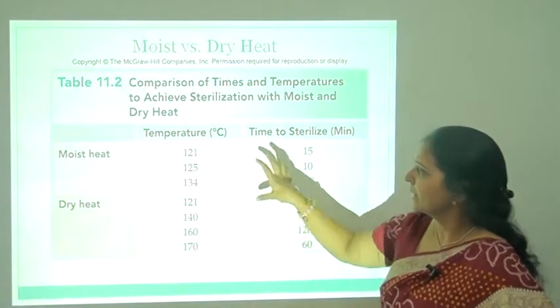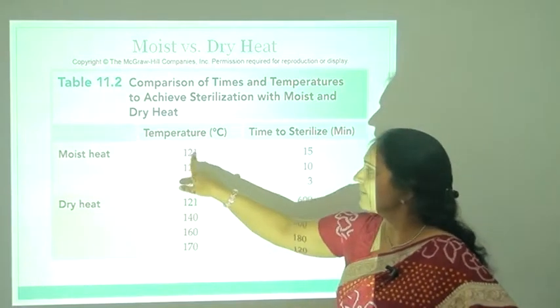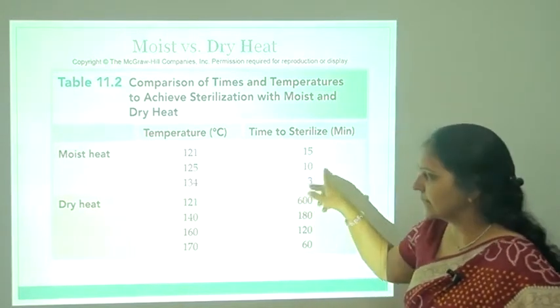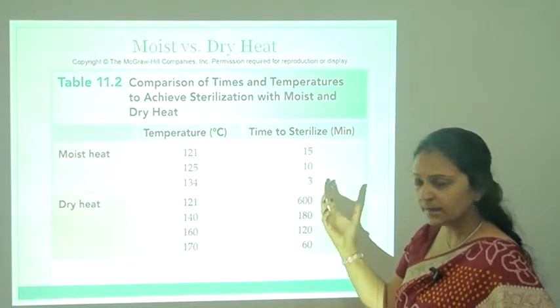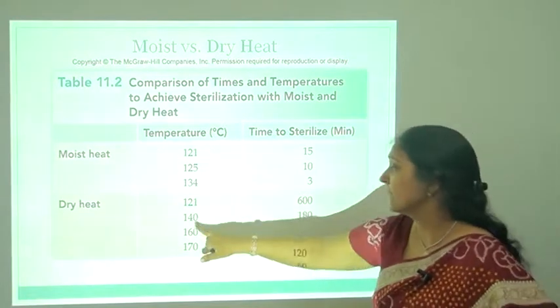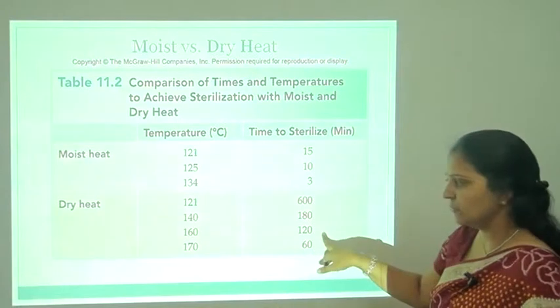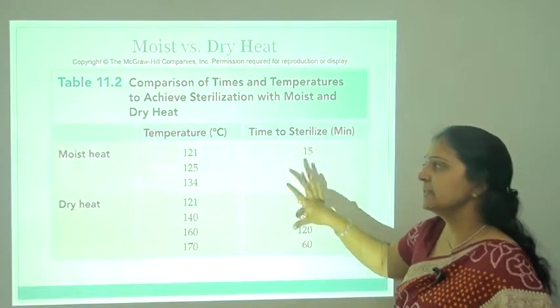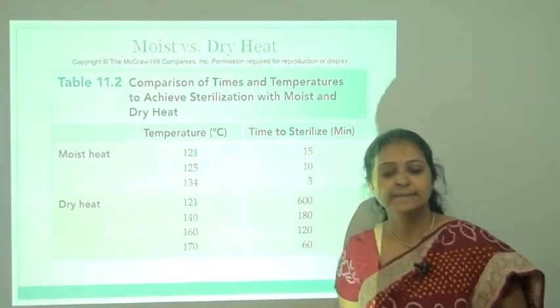Comparing moist heat and dry heat: moist heat requires 121°C for 15 minutes, 125°C for 10 minutes, and 134°C for only 3 minutes for sterilization. Dry heat requires 121°C for 600 minutes, 140°C for 180 minutes, 160°C for 120 minutes, and 170°C for 60 minutes. From this comparison we can observe that moist heat is more effective than dry heat.